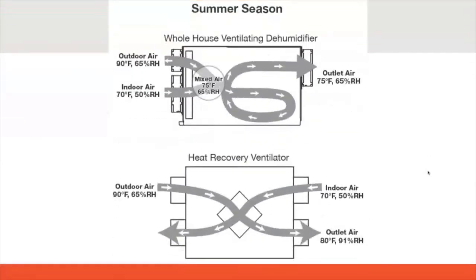If we look at it during the summer season, we've got 90-degree air outside and that dehumidifier is going to deliver 75-degree air because again, we're mixing with the living space air. And the HRV would deliver about 80-degree air. So still it's a very effective ventilation strategy that's not going to add a tremendous amount of sensible load on the house or the living space, different than what an ERV or an HRV would do.